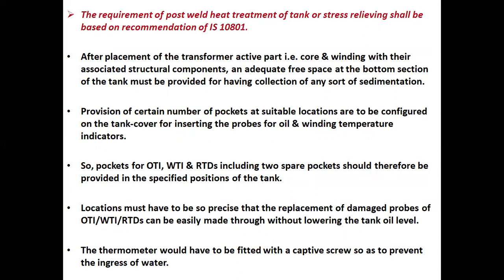A certain number of pockets at suitable locations are to be configured on the tank cover for inserting the probes for oil and winding temperature indicators. So, pockets for OTI, WTI, and RTDs, including 2 spare pockets, should be provided in the specified positions of the tank. Locations must be precise so that replacement of damaged probes of OTI, WTI, RTDs can be easily made without lowering the tank oil level. The thermometer would have to be fitted with a captive screw to prevent the ingress of water.